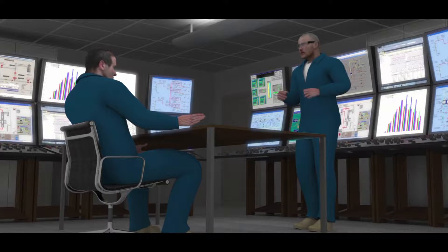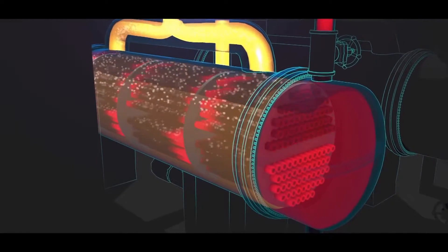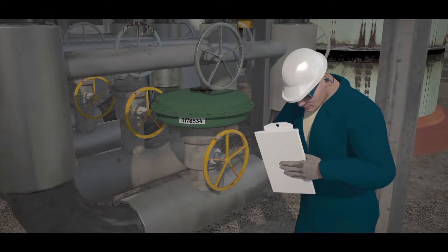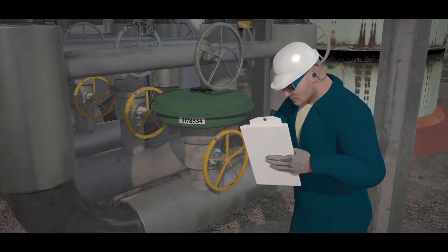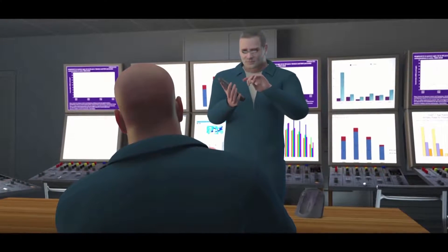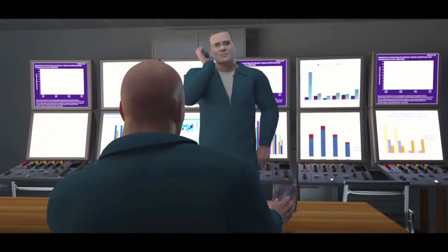On June 13, 2013, during a daily meeting with operations and maintenance personnel, the Williams plant manager noticed that the water flow rate through the operating re-boiler had dropped gradually over the past day. The operations supervisor informed the group he would try to identify the problem. He went into the plant to evaluate the water flow rates and informed several personnel that fouling within the operating re-boiler could be the problem, and they might need to switch the re-boilers. He attempted to meet with his manager to get the necessary personnel involved, but his manager was not available.